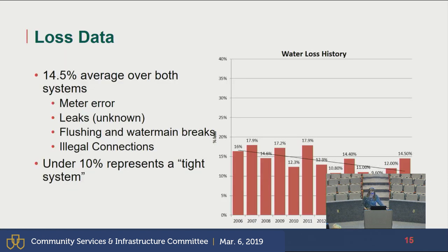Going over water loss, you will see an increase this year, actually over the past 2 years, in our water loss. This is primarily tied to meter error. And in April, you see it brought forward. I think a number are aware we will be going through the program to replace all the meters. A lot of our meters are outside of their accurate reading age, and we're seeing a significant decline in accuracy, so they're underestimating how much water is being used.